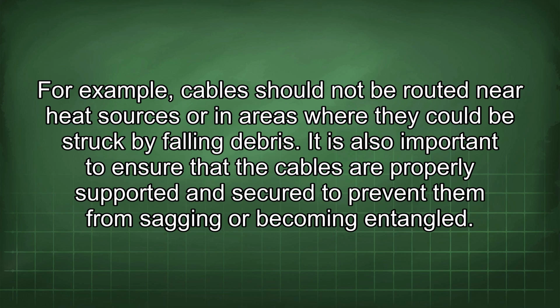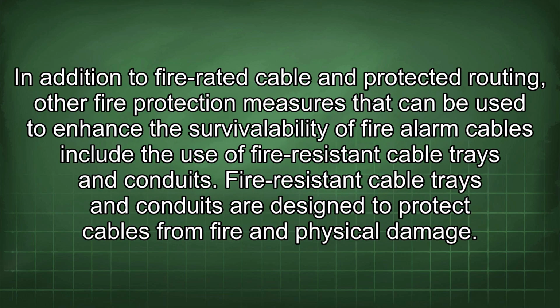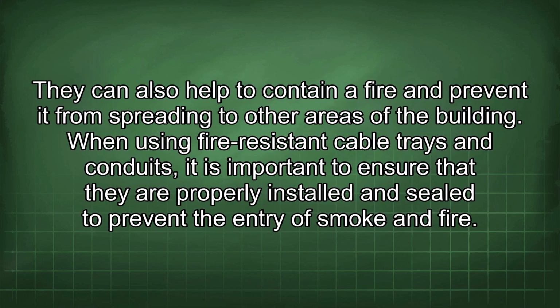In addition to fire-rated cable and protected routing, other fire protection measures that can be used to enhance the survivability of fire alarm cables include the use of fire-resistant cable trays and conduits. Fire-resistant cable trays and conduits are designed to protect cables from fire and physical damage. They can also help to contain a fire and prevent it from spreading to other areas of the building. When using fire-resistant cable trays and conduits, it is important to ensure that they are properly installed and sealed to prevent the entry of smoke and fire.